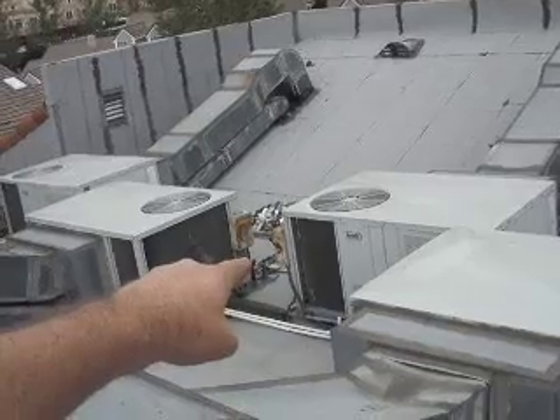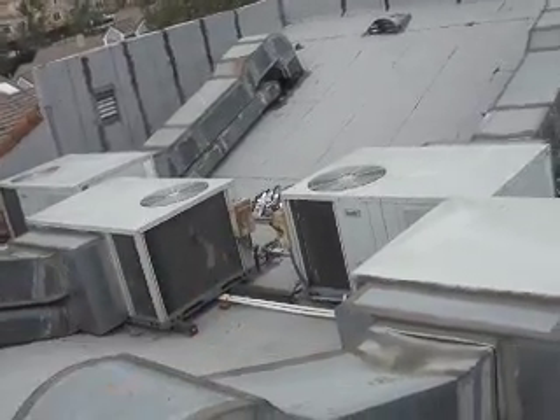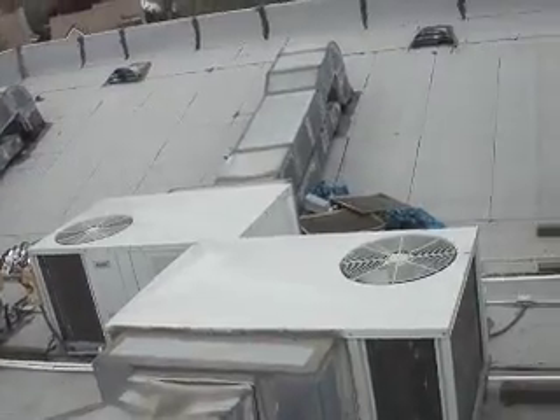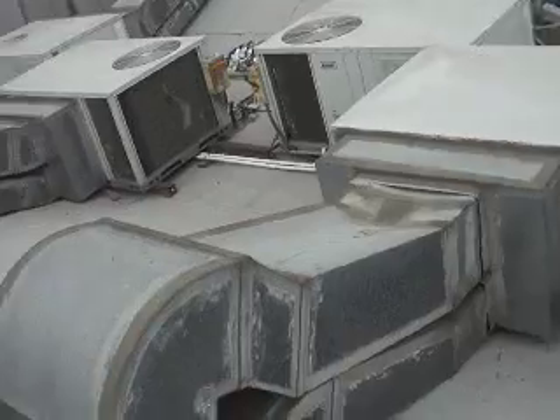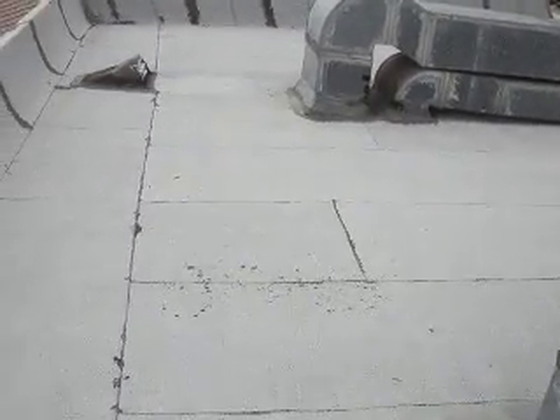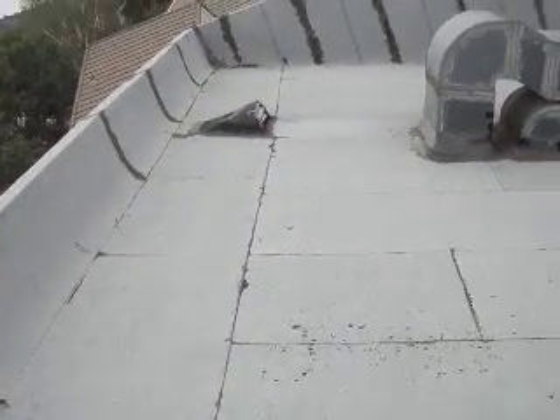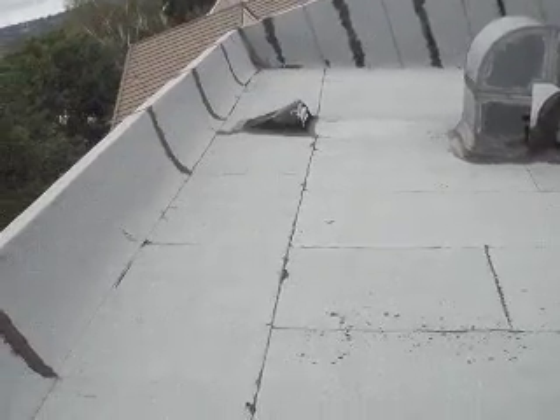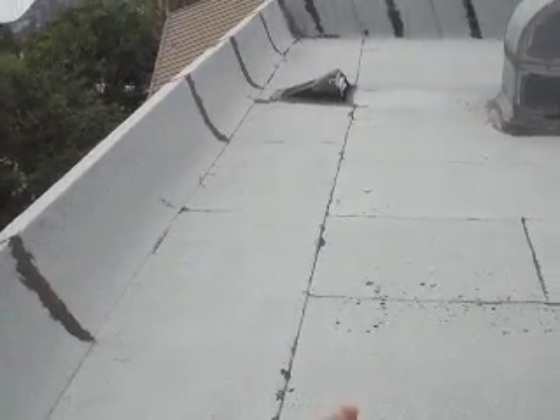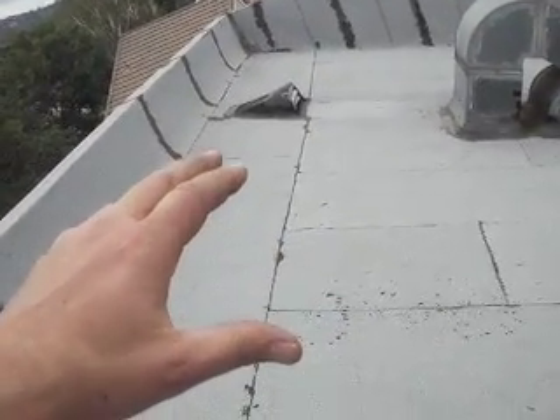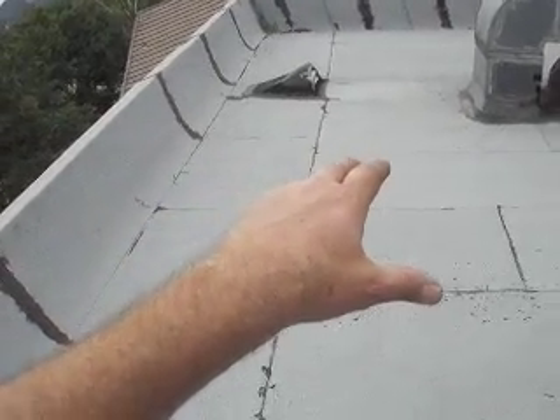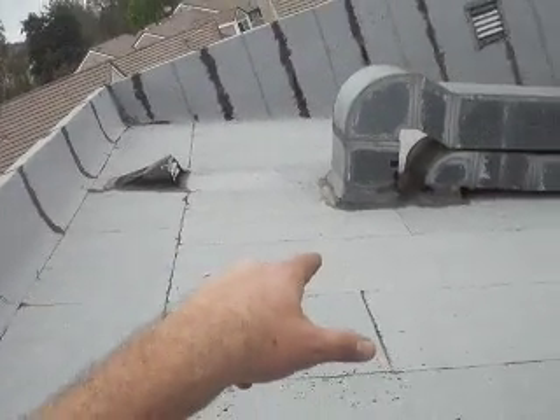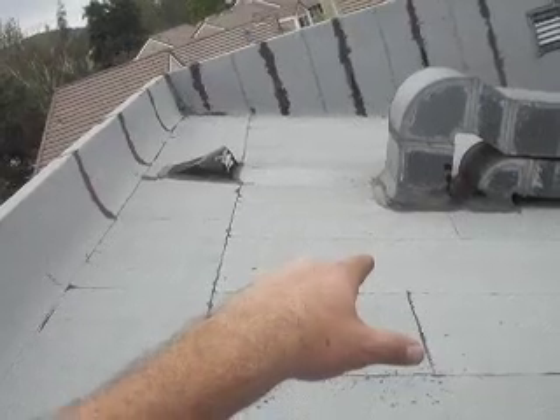This one right here is, again, we'd replace that one as well. So I really recommend replacing 4 of them, or I could recondition them. But the main concern and what's really labor intensive is the inside ducting. It really needs to all be changed out and reconfigured as far as for noise, and it's kind of choked off because really this ducting is a little bit undersized for these 5-ton units.